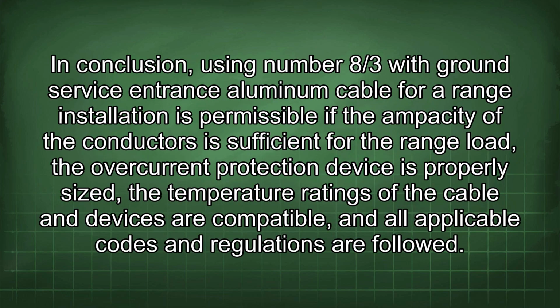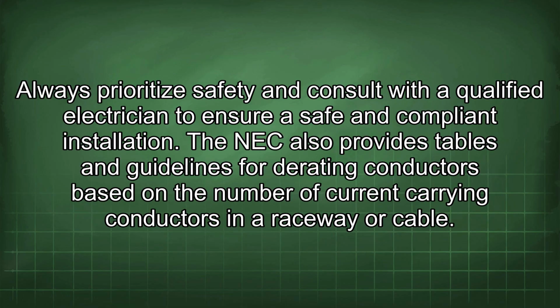In conclusion, using number 8/3 with ground service entrance aluminum cable for a range installation is permissible if the ampacity of the conductors is sufficient for the range load, the overcurrent protection device is properly sized, the temperature ratings of the cable and devices are compatible, and all applicable codes and regulations are followed. Always prioritize safety and consult with a qualified electrician to ensure a safe and compliant installation.